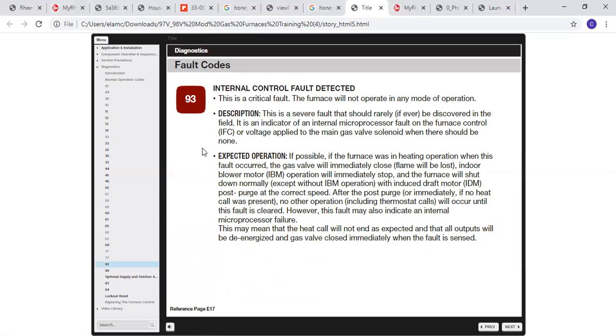And the number 93, the internal control fault detected. This is a critical fault. Occasionally you'll see this. Generally speaking, it's found to be a board. Basically, it's a fault within the internal microprocessor. I've had a couple of them where you could actually switch the low voltage transformer leads, and that seemed to fix it. That was the phasing that was causing that.